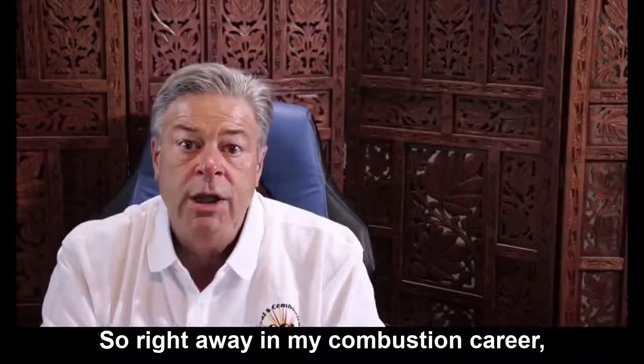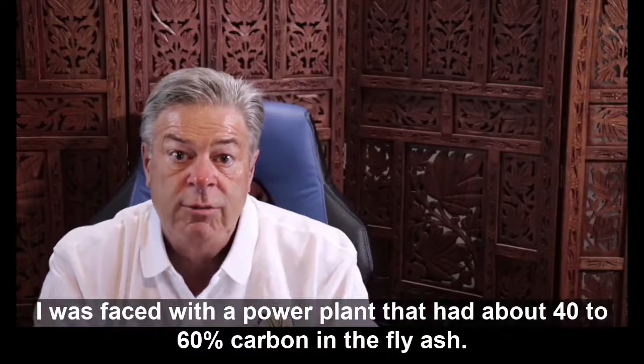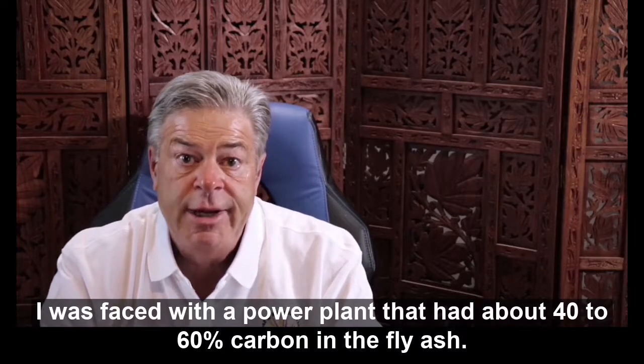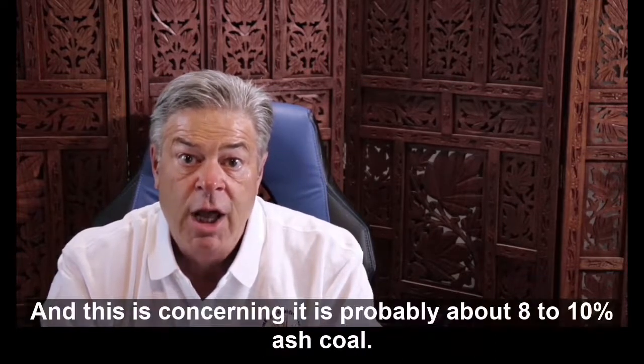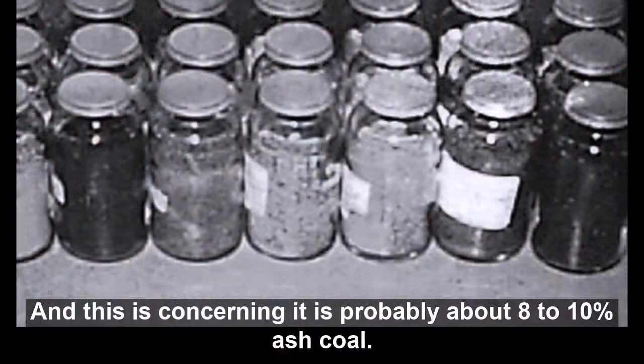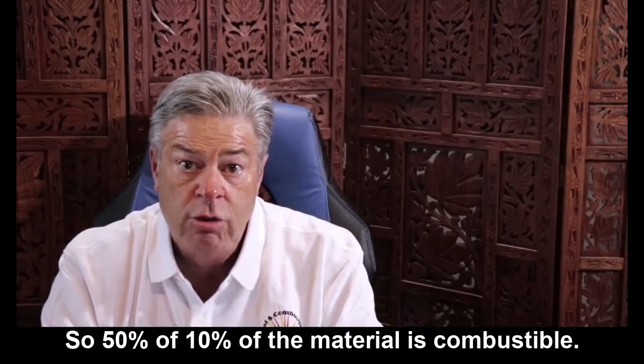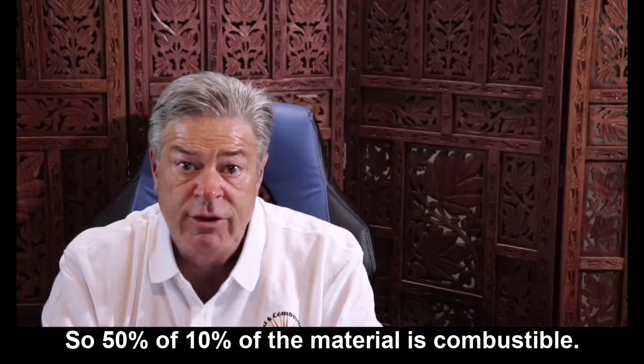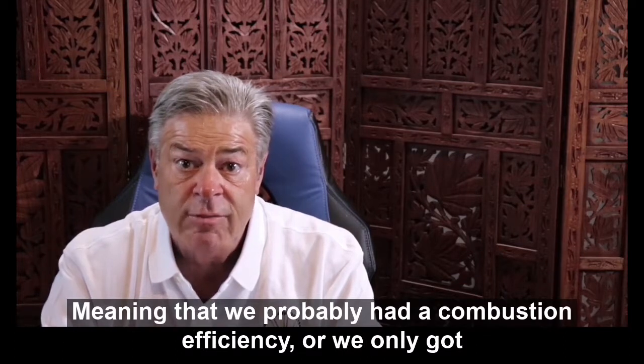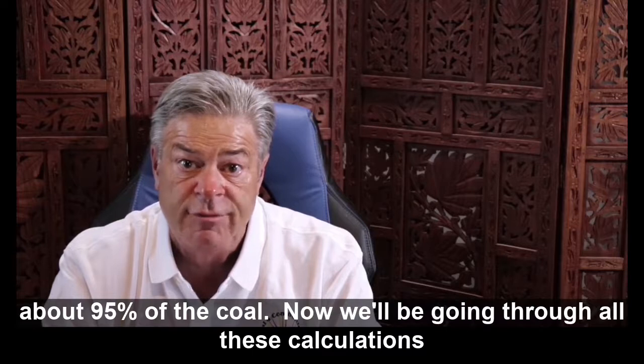So right away in my combustion career, I was faced with a power plant that had about 40 to 60% carbon in the fly ash. And this is concerning. It is probably about an 8 to 10% ash coal, so 50% of 10% of the material is combustible, meaning that we probably had a combustion efficiency where we only got about 95% of the coal.